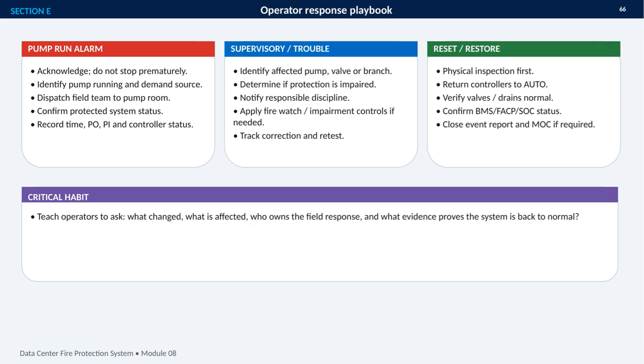For supervisory or trouble conditions, I identify the affected pump, valve, or branch, then determine whether fire protection is impaired. The responsible discipline must be notified, and fire watch or other impairment controls applied when necessary. Corrections should be tracked through retest. Reset and restoration begin with a physical inspection, not simply clearing the alarm. Controllers return to auto, valves and drains are verified normal, and BMS, FACP, and SOC status are confirmed. The event report, and MOC when required, must then be closed.